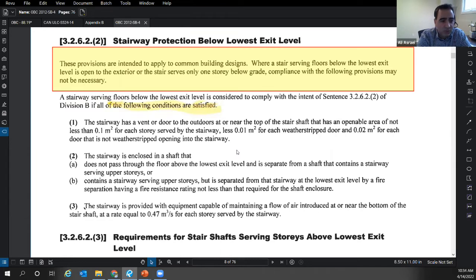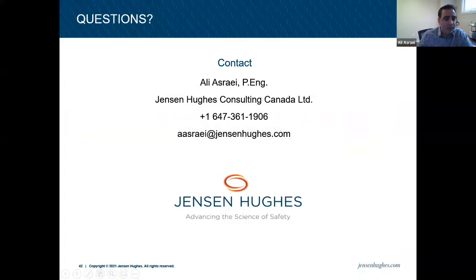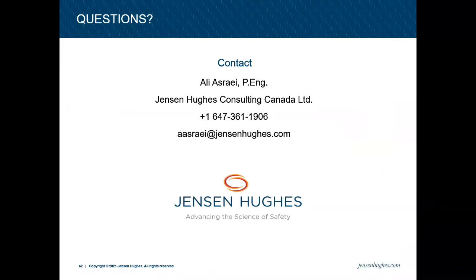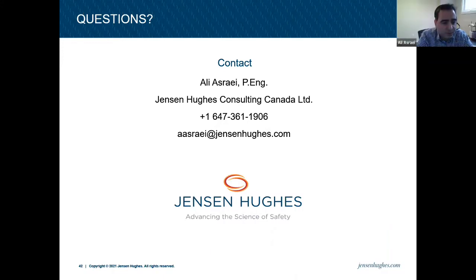So technically for one story, I've seen that, and what do you want to do? You pressurize it right away, there's one landing above, you basically have to vent it out, right? So technically that gives you permission. It's not about the direct exiting to the exterior. It's more about if it's serving one story or less, right? Yeah. Okay.